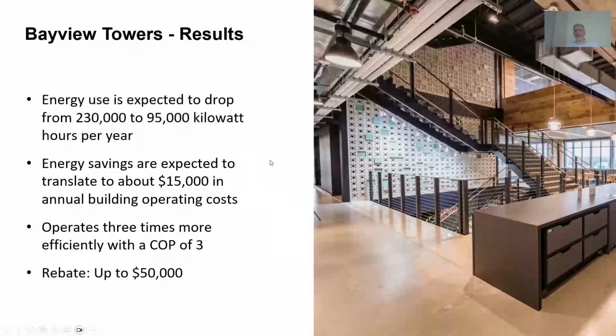Since it was initially an electric facility, there is a reduction of power usage, from around 230 to 95 kilowatts. Converting to the electric rates, you end up saving around $15,000 annually on the building cost. And since it's a heat pump, on average they were having a COP of 3. That means you are reducing your power input to one third, or, looking at it the other way around, with the same power input you're getting three times the output.